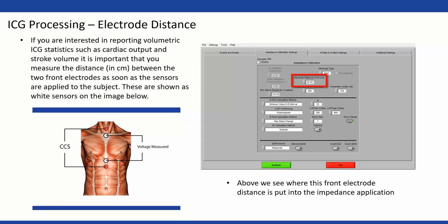One more thing on calibration settings: if you're looking to report on volumetric measures like stroke volume and cardiac output, it's very important that during acquisition the experimenter measures the distance between the two white front sensors. We need to know the thorax size to estimate blood volume. Make sure you're recording that distance and entering it into the impedance calibration settings. If you're using band electrodes rather than spot electrodes, you'll also need to take the back distance — there are two measurements needed. But for most people we're using spot, so just that front distance.